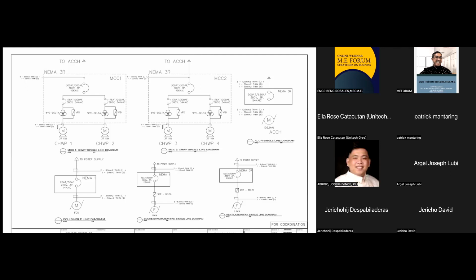Now, in each MCC, we have a disconnection switch and individual breakers. The disconnection switch is just for protection purposes. If we look at it, it shows the ampere trip, ampere frame, the voltage 380, and you can see 3P on our MCCs. 3P basically means 3-pole. If 3-phase, it's 3-pole; if single phase, it's 2-pole. What pole means in layman's term is the wire that goes in. Single phase uses two wires, so 2-pole. 3-phase uses three wires for the line, so 3-pole.